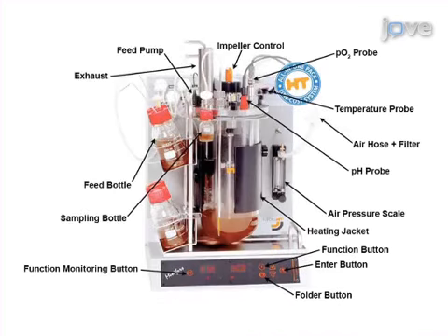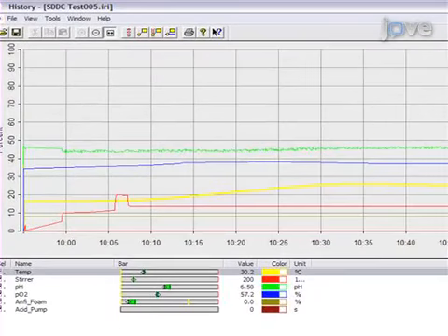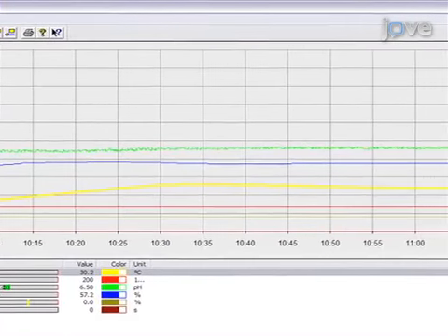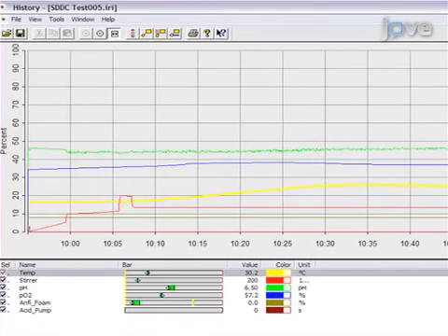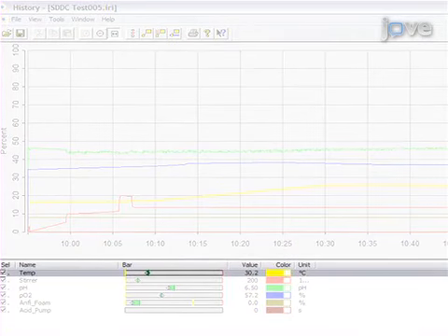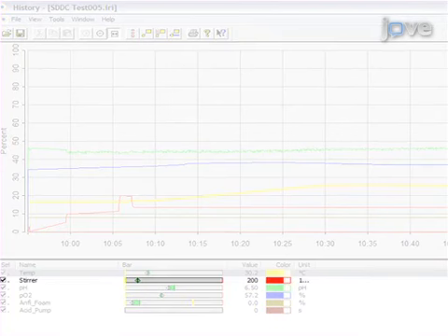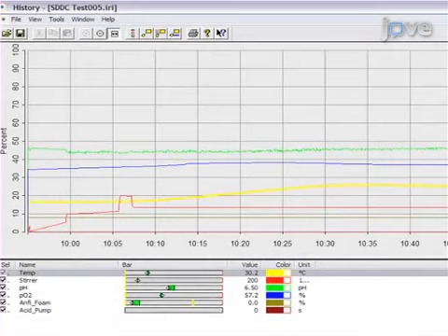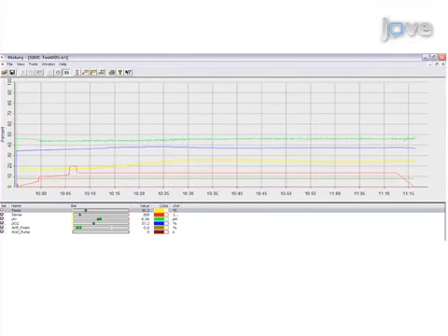In this video, the setup and operation of a typical benchtop bioreactor system was demonstrated. This figure shows the bioreactor at the beginning of a run, with all parts labeled and connected. The data output for a representative bioreactor run is presented in this figure. At the start of a stirred tank run, the temperature was set at 30 degrees Celsius, impeller speed at 200 RPM, pH at 6.5, and oxygen at 57.2%. The parameters may be different for each experiment, but before addition of bacteria, the system should be at steady state.